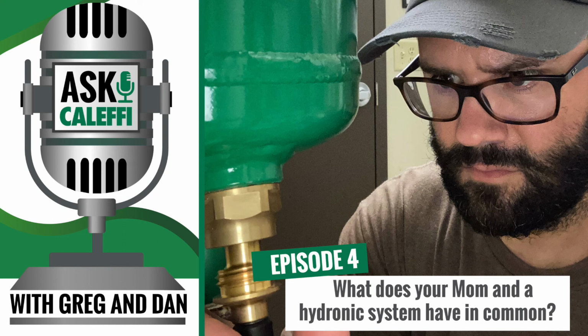The thing to remember with those, like the vertical air separators we talked about last week, is the lower flow capacities, only up to about 10 gallons per minute. Sure. And again, that's because that one is not a direct pass-through device. So from installation to now maintenance, we walk people through a maintenance procedure all the time on these, don't we? We do. The key to anything is going to be maintenance. So you want to make sure that you get the system cleaned up and then you're able to put it on a maintenance cycle.